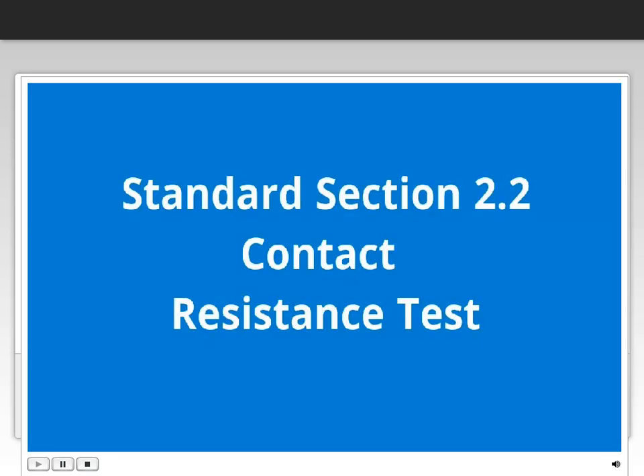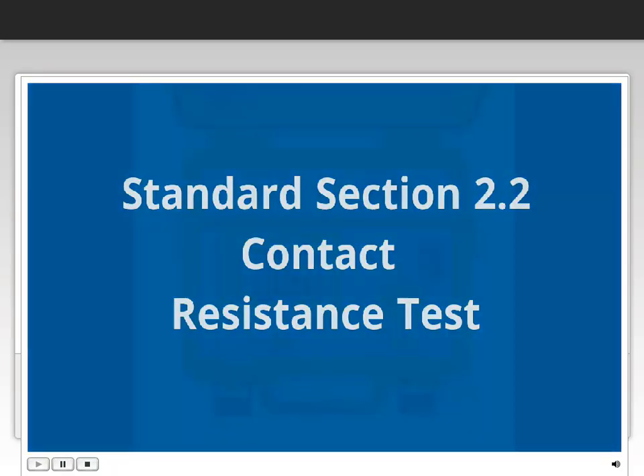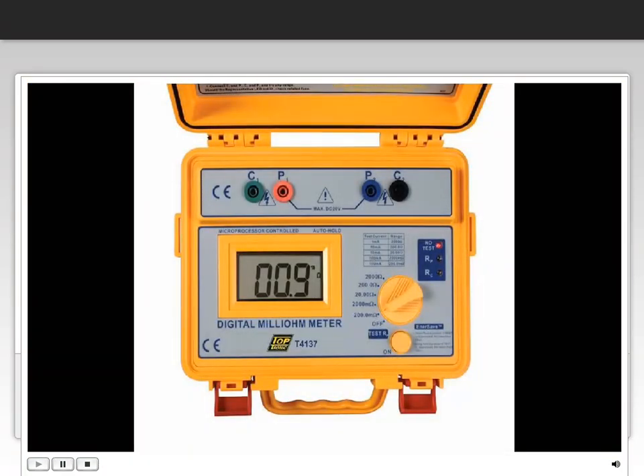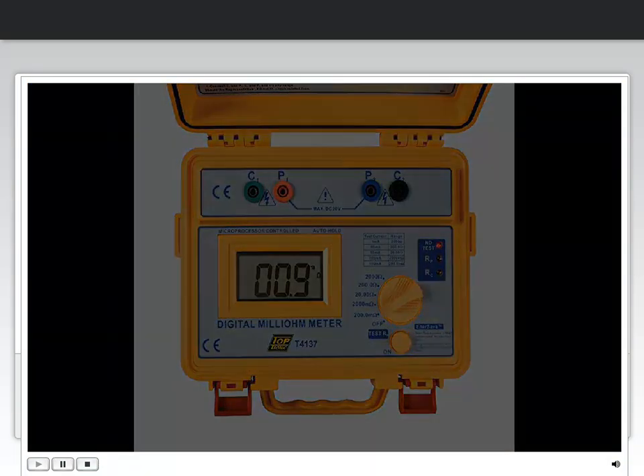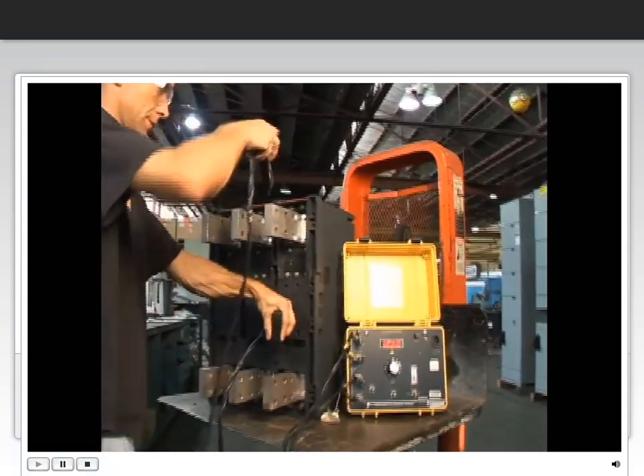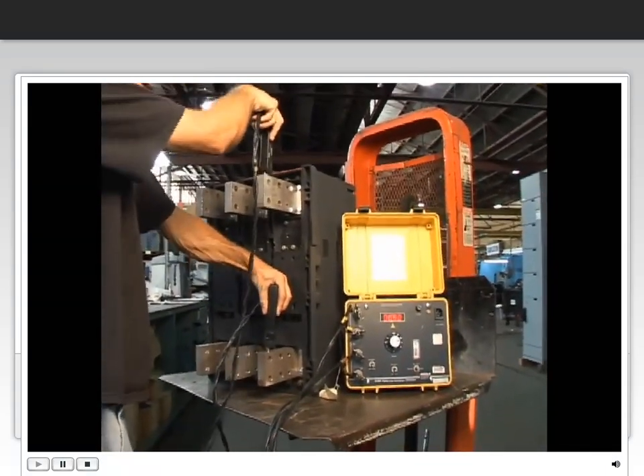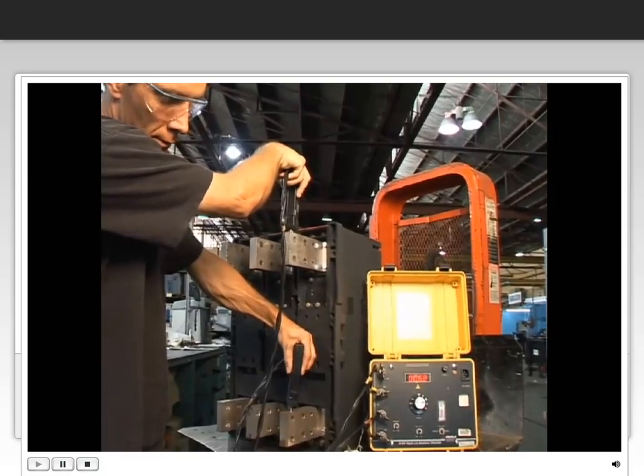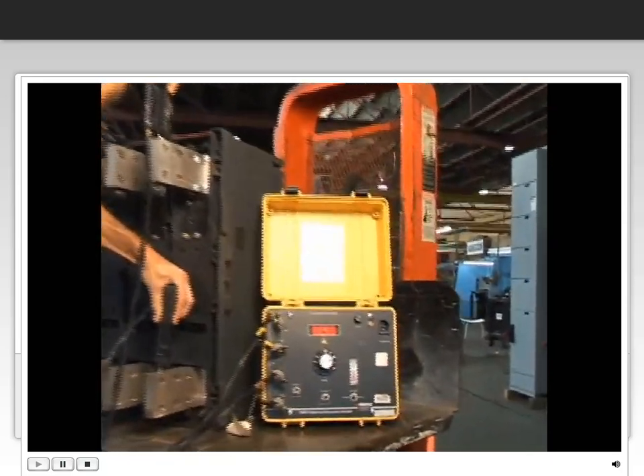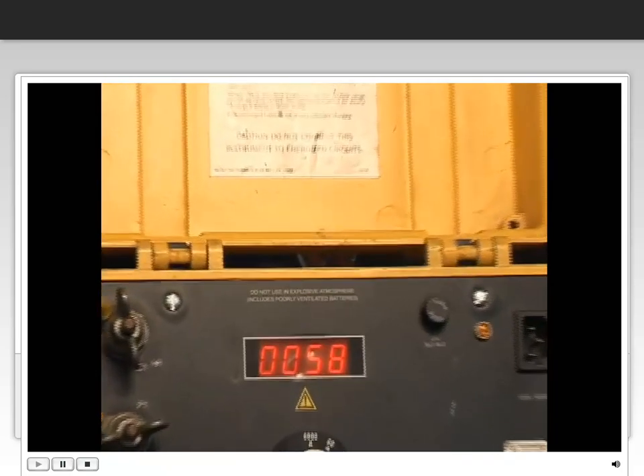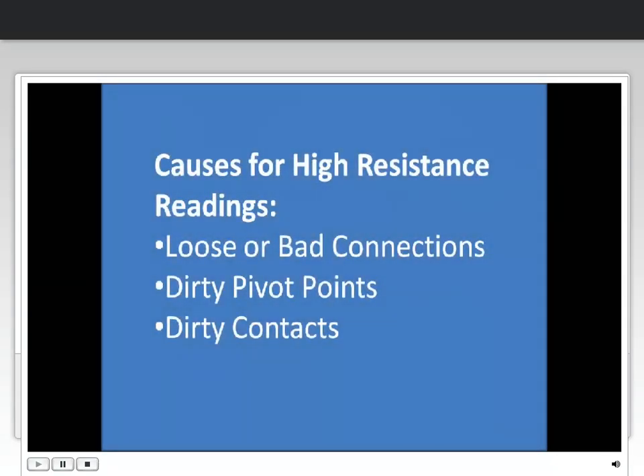A contact resistance test using a digital low resistance ohm meter or a millivolt drop test from line to load on each phase of a closed breaker. A known current is applied across the current carrying path of the breaker, and the drop across the path is measured. This test will check the current path resistance of the circuit breaker. Loose or bad connections, dirty pivot points, and dirty contacts will show up as a high resistance reading. Any of the points that have a high resistance could have excessive heating and possibly arcing that could damage the breaker.